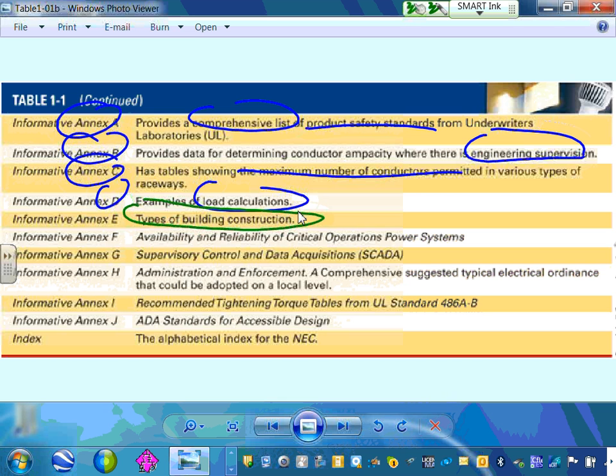You wouldn't use Romex in type 1 construction—it's approved typically for wood, so wood construction for the most part. Inside a block building like this, you can't use it; it's not approved. So if you have construction like this, you'd use an MC cable or AC cable instead, and we'll talk about wiring methods as we go. These are the cheapest wiring methods you can use, other than barbed wire—which might actually be more expensive. This is the cheapest wiring method, and that's what we use in dwellings all the time.